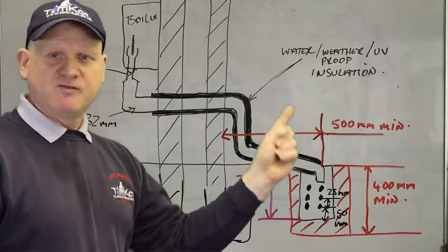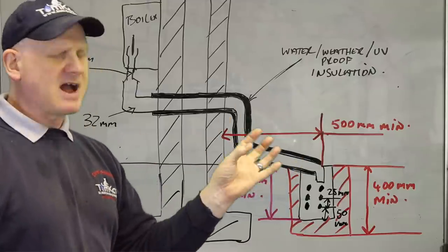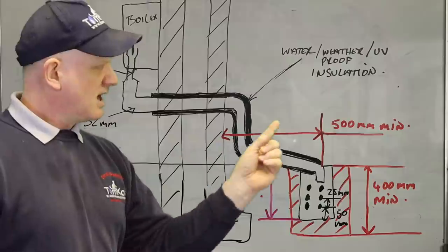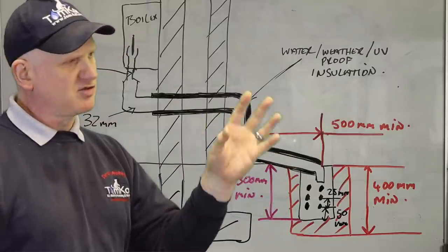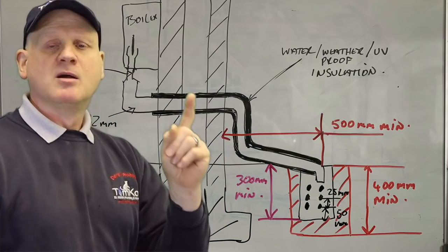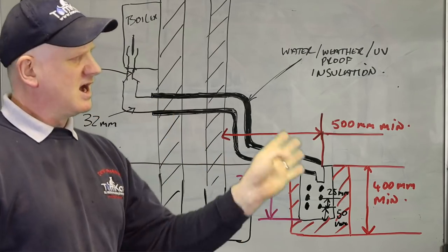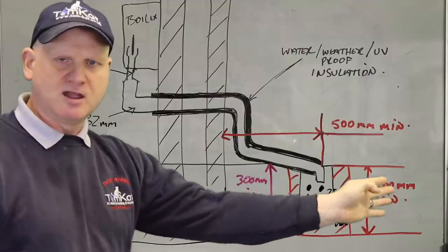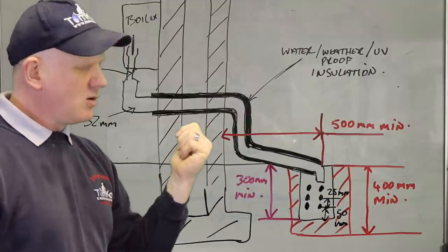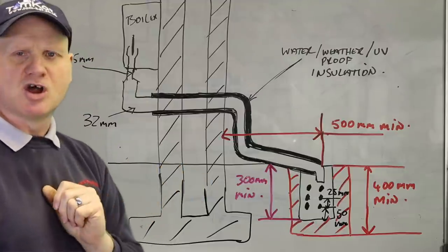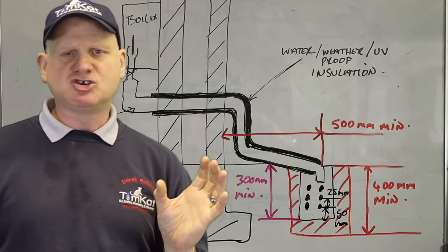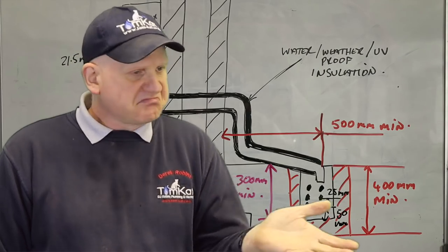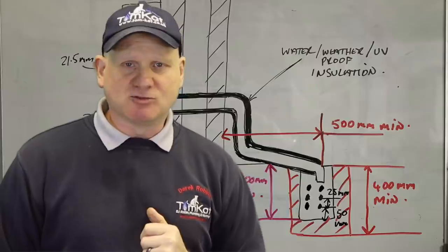So our hole is 400 millimetres deep, but our actual purpose-made soak-away tube is 300 millimetres minimum in length. And the holes there are evenly spaced at 25 millimetres apart in all directions, but at least 50 millimetres off the bottom. And you will put that at the front of the tube, so it's directing the condensate away from the house. So that's basically how you install a soak away. Done it on numerous occasions. They're pretty cheap to buy and they're purpose made plastic tubes really, which you fill with limestone chippings.